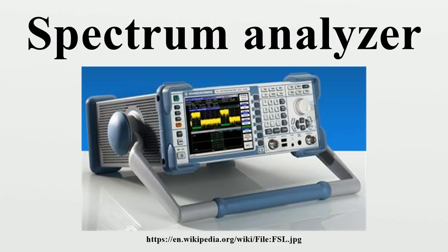Spectrum analyzers can also be used to assess RF shielding. RF shielding is of particular importance for the siting of a magnetic resonance imaging machine, since stray RF fields would result in artifacts in an MR image. Audio frequency uses.